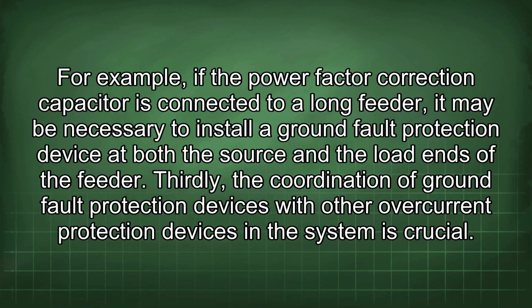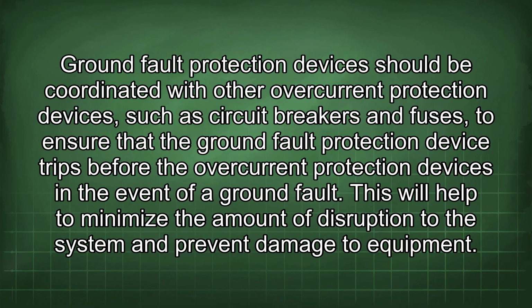Thirdly, coordination of ground fault protection devices with other overcurrent protection devices in the system is crucial. Ground fault protection devices should be coordinated with other overcurrent protection devices, such as circuit breakers and fuses, to ensure that the ground fault protection device trips before the overcurrent protection devices in the event of a ground fault. This will help to minimize the amount of disruption to the system and prevent damage to equipment.